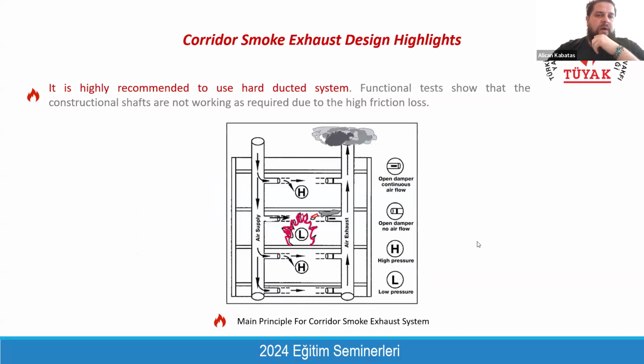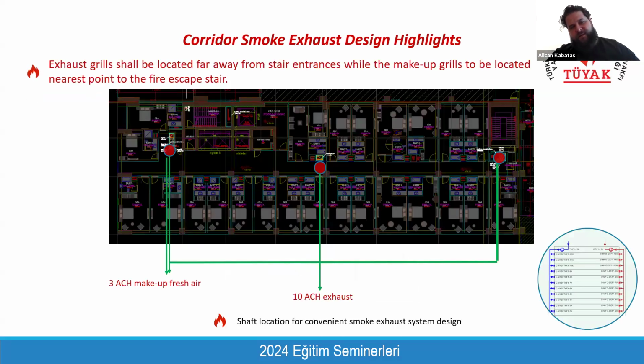And as we told, for some situations, for high-rise buildings or for hotels and dormitories, we will have a corridor smoke exhaust system design, and this system should have a smoke shaft, and also, in order to achieve smoke extraction, we need to have a fresh air shaft as well. We need to provide fresh air, and then we need to extract it from the floor. It means we will have at least two additional shafts, and the dimensions of these vertical shafts depend on the capacities of the smoke extraction system. And the locations are really important.